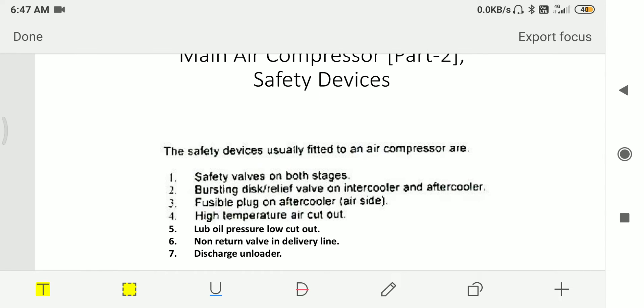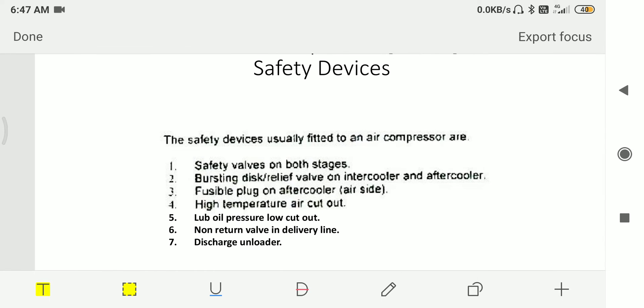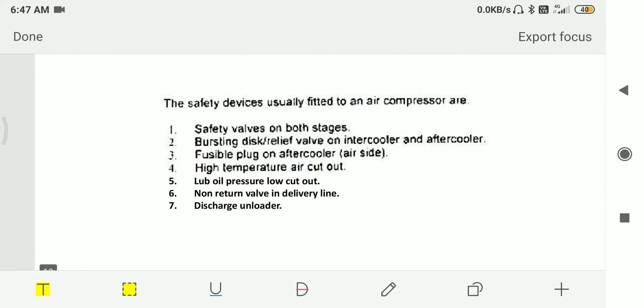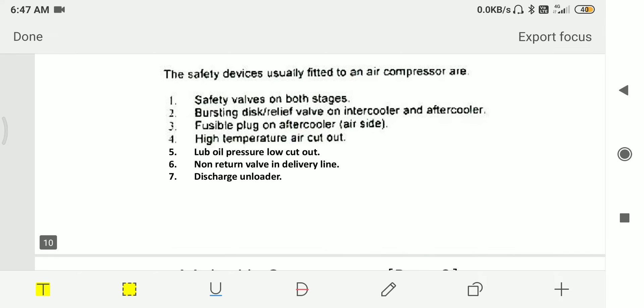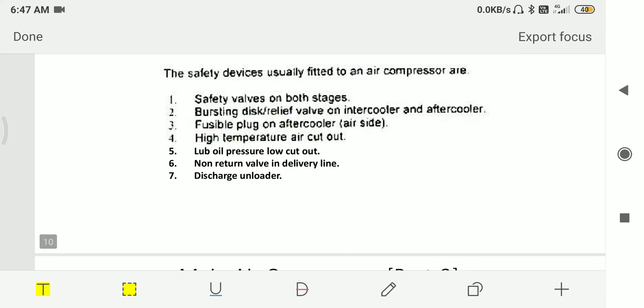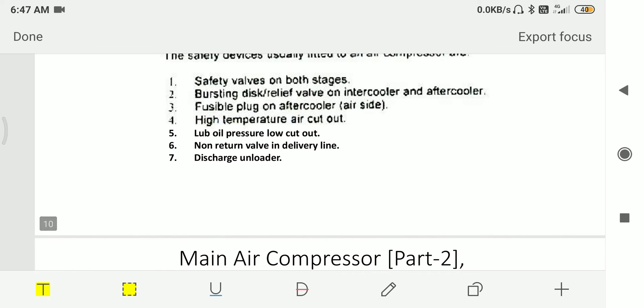Then I will tell you about safety devices which are incorporated in the compressors for safe operation. That is safety valves on both stages, bursting disc or relief valve on the intercooler and aftercooler, fusible plug on aftercooler air side, high temperature air cutout, low oil pressure cutout, non-return valve in the delivery line, and discharge unloader.